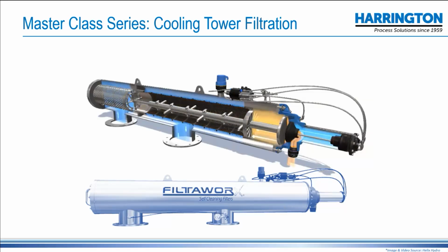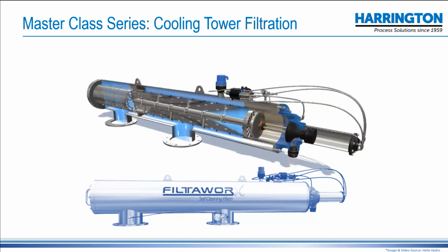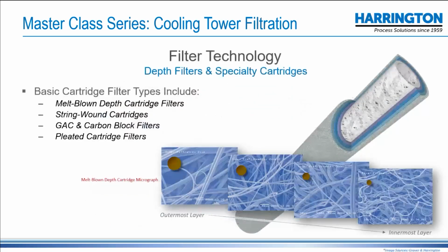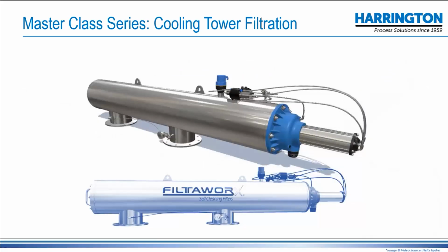As I mentioned, we can get screens down to the 10 micron range. For cooling tower purposes, a spray nozzle has an 80 micron orifice. So I think probably the best target would be a 50 micron screen. You can use those in virtually any of the filtration scenarios that we've talked about.